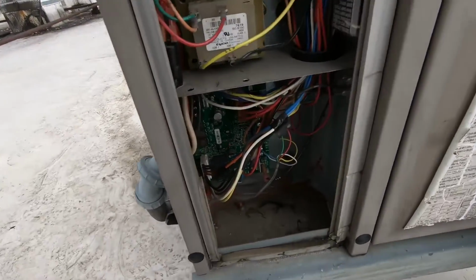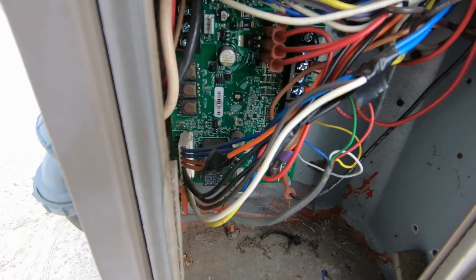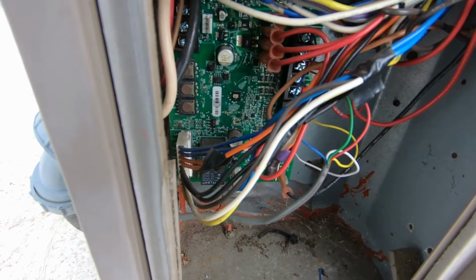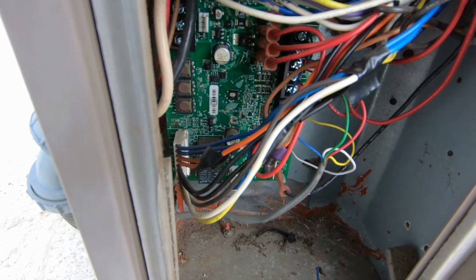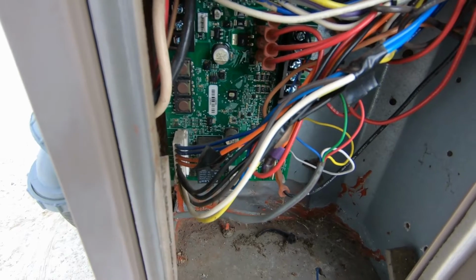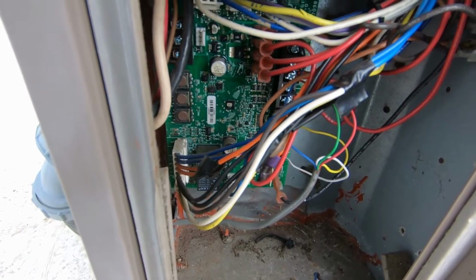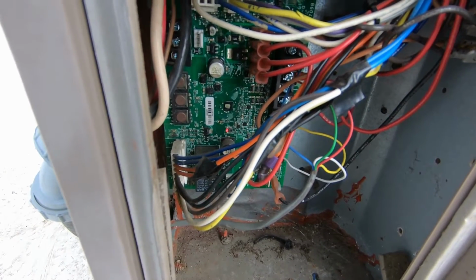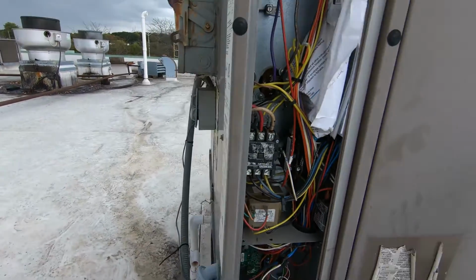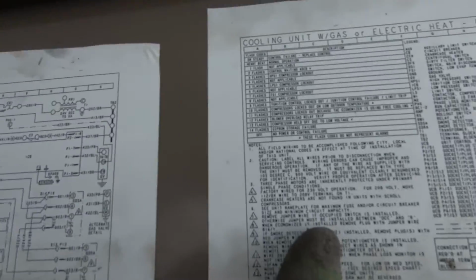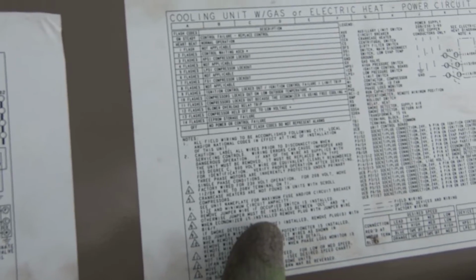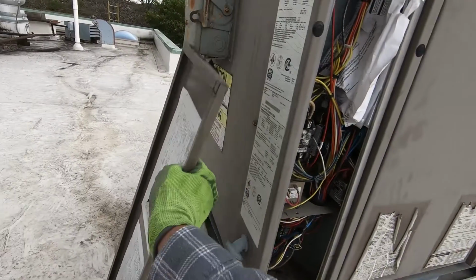All right, guys, we've got a flash code here. 1, 2, 3, 4, 5, 6, 7, 8, 9. Ignition control locked out, ignition control failure, or limit switch.